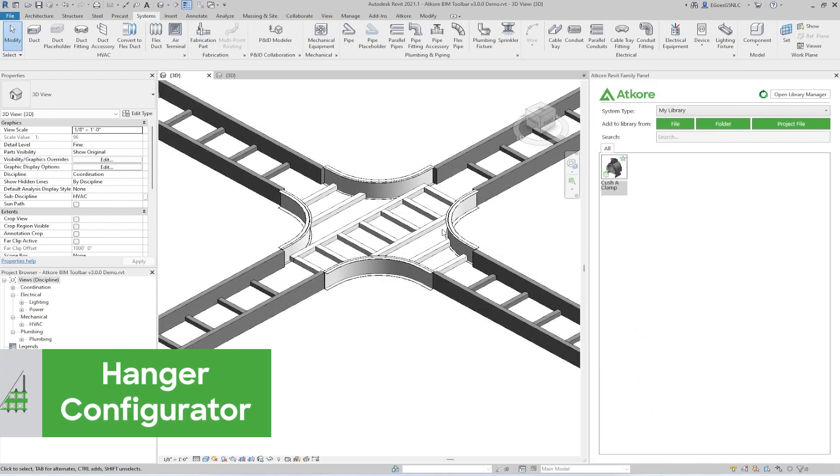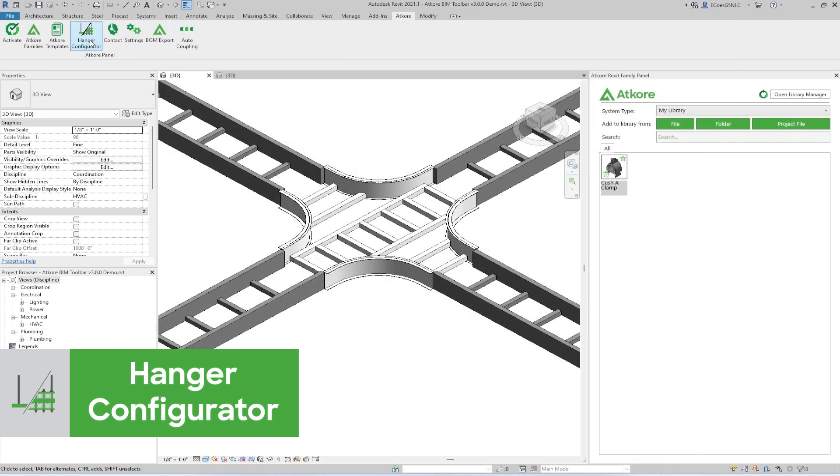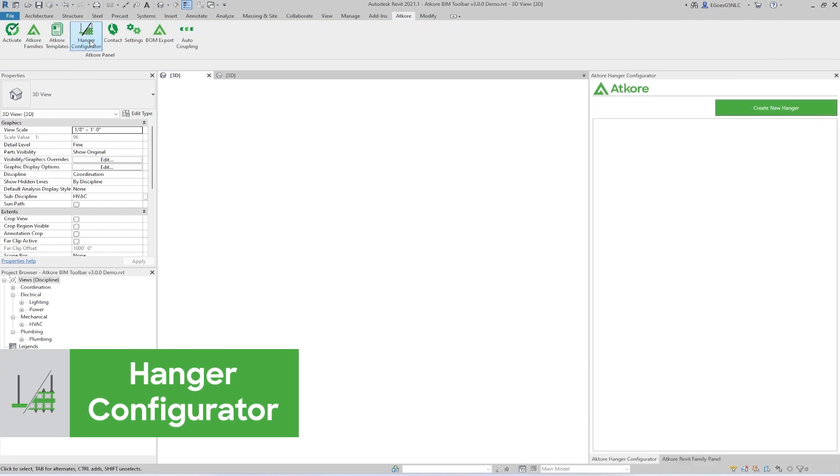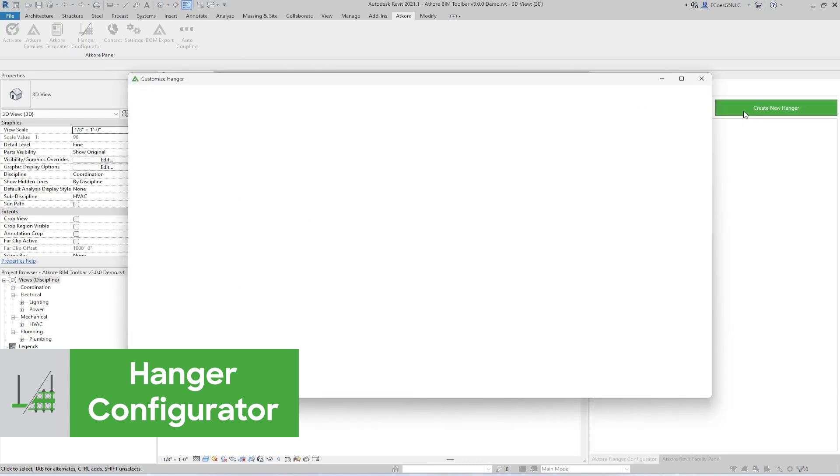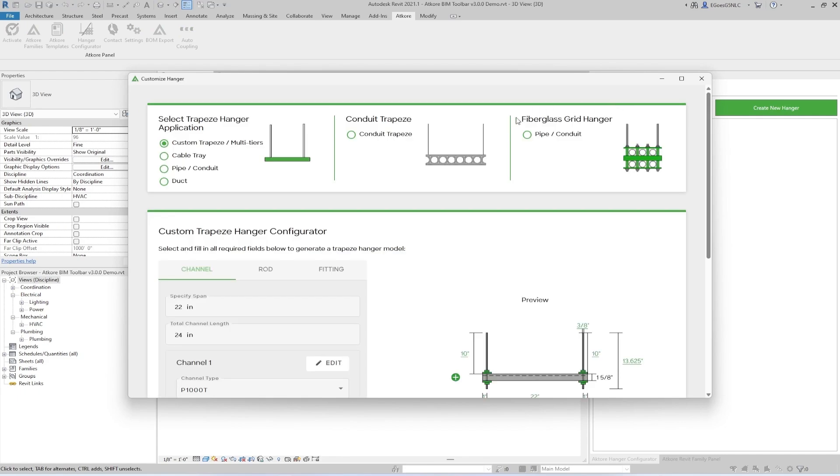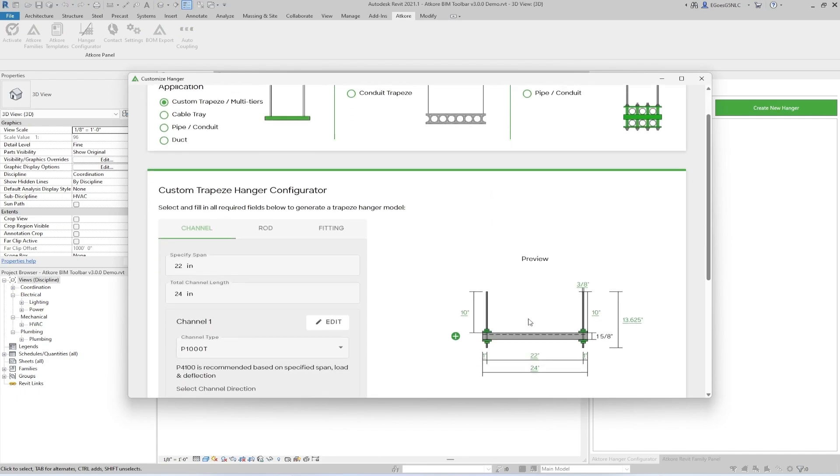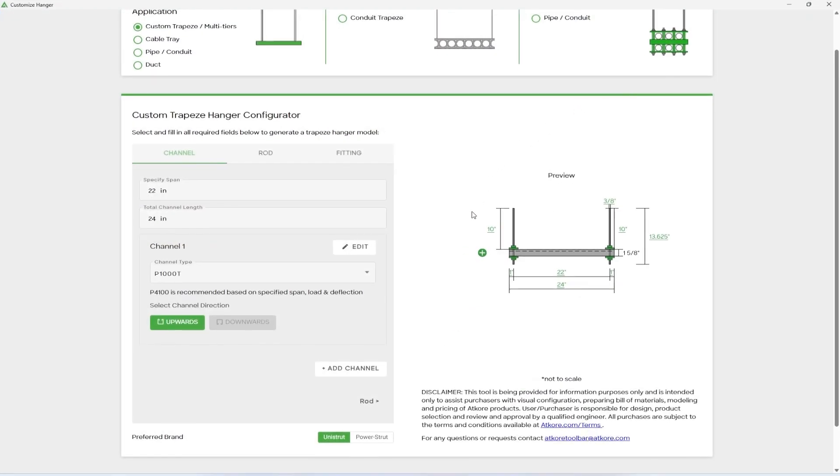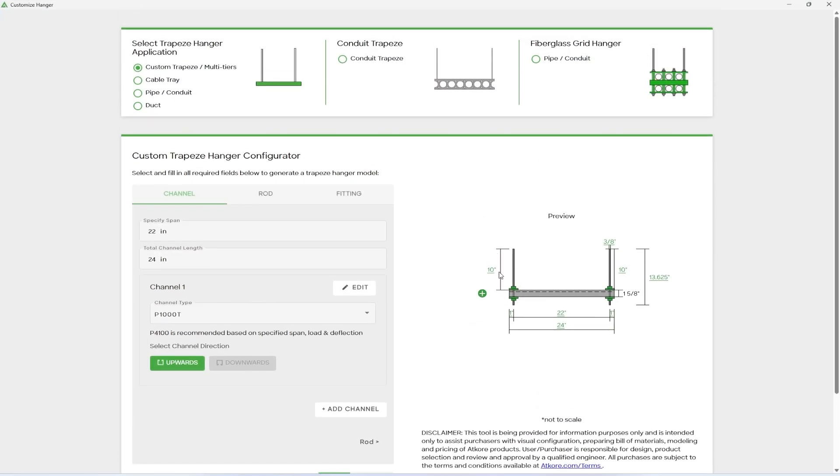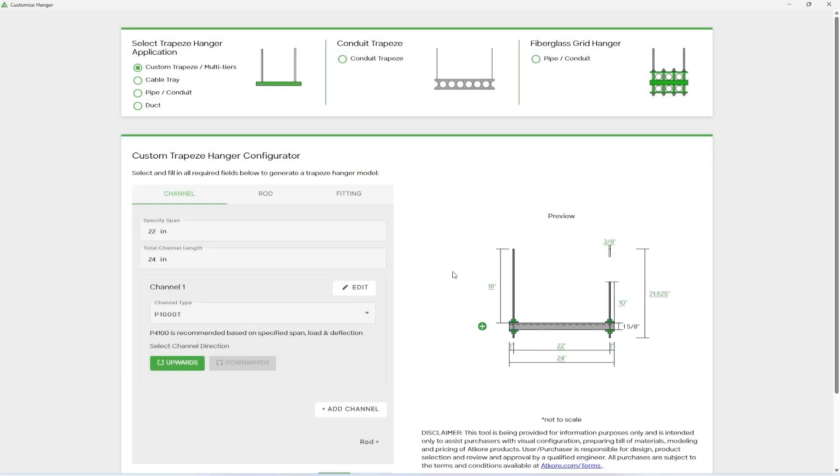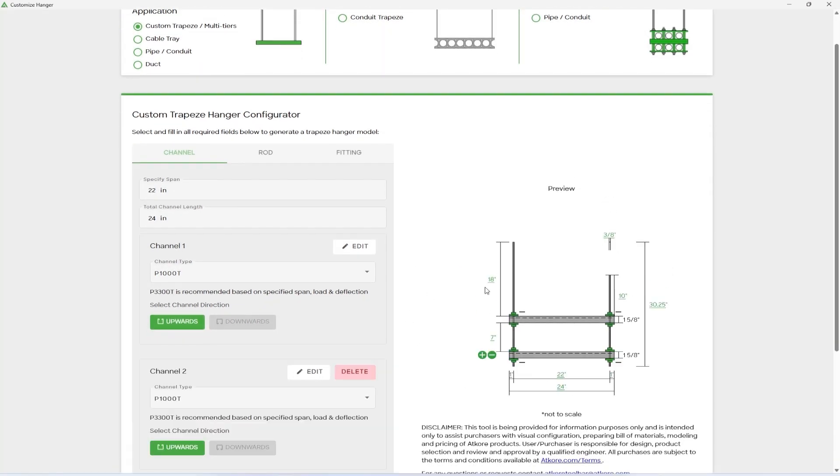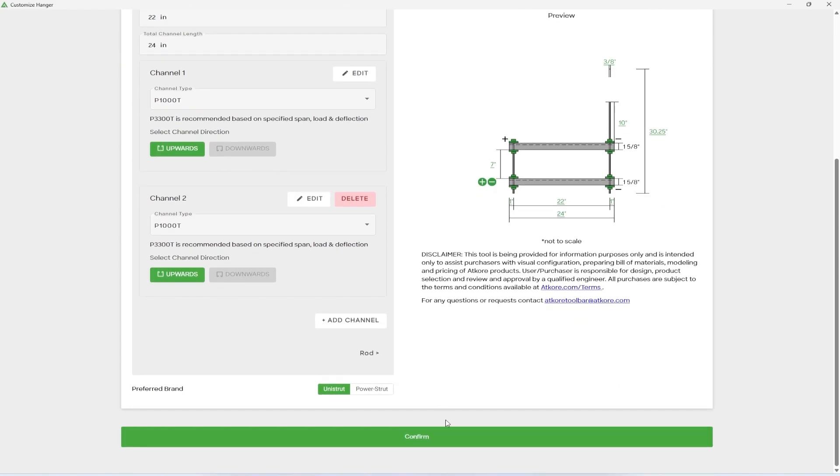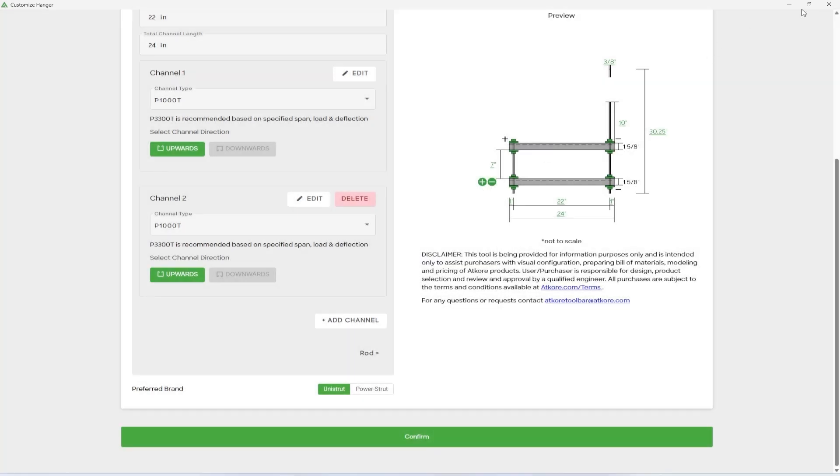Next we have the Hanger Configurator. Once again, clicking this button will open a panel inside Revit. There are two main methodologies for creating a hanger. The first is just by clicking Create New Hanger, and then configuring the Trapeze Hanger to best suit your needs. Any of these green dimensions can be clicked on and adjusted, like so, and the plus and minus icons will add or remove tiers or connections. Once finished, go down to the Confirm button, and then you can name it whatever you want. After it's configured, it can then be placed manually.